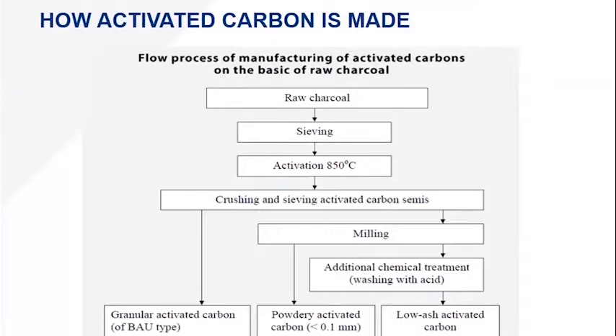One of those additional steps is chemical treatment — typically acid washing the carbon. What the acid wash does is pull those heavy metals out of the pore structure of the activated carbon, purifying it and keeping it from releasing those contaminants during treatment. You then have a low-ash activated carbon because that acid washing also removes the ash from the carbon. This is where you get your standard chlorine-type removal activated carbon.